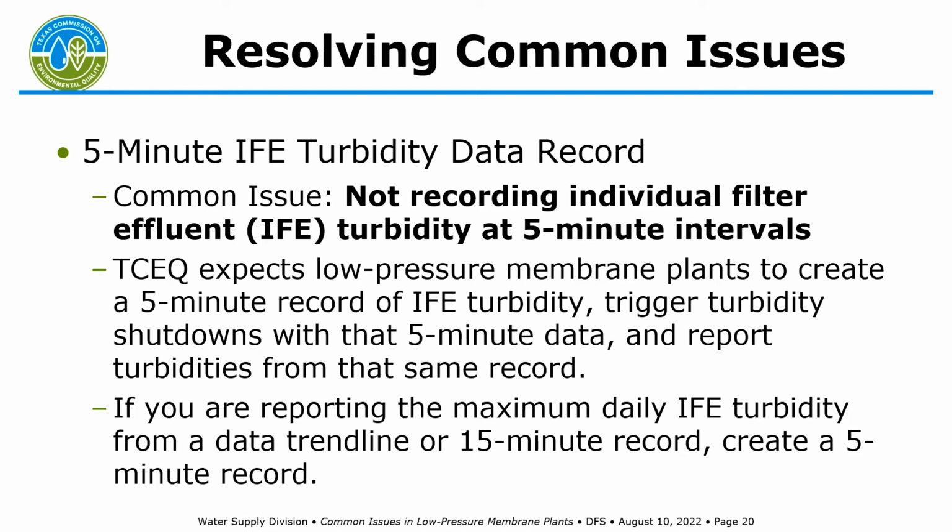We've actually created a template on that same website where the checklist and the common issues document are. It's just a template of, here's an example of how you can set up a 5-minute record, of what records should go into this. And the cool thing about our template, and you can have your contractor do it just as well, is you enter in all the 5-minute data, and then the spreadsheet tells you, all right, here are the values you need to report in the SWMOR.